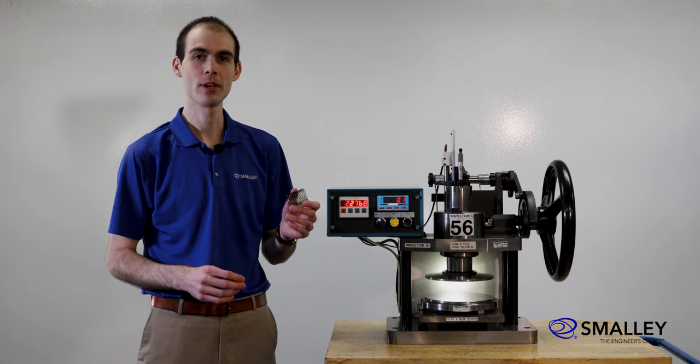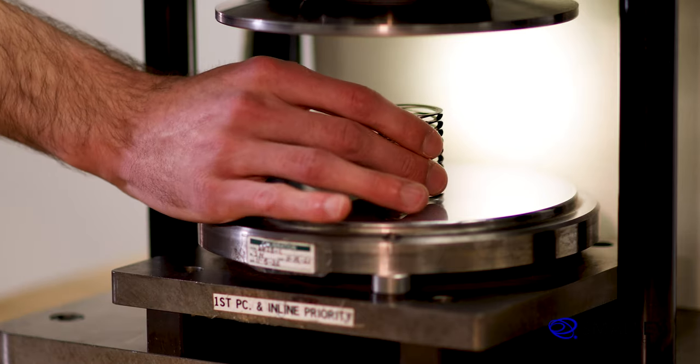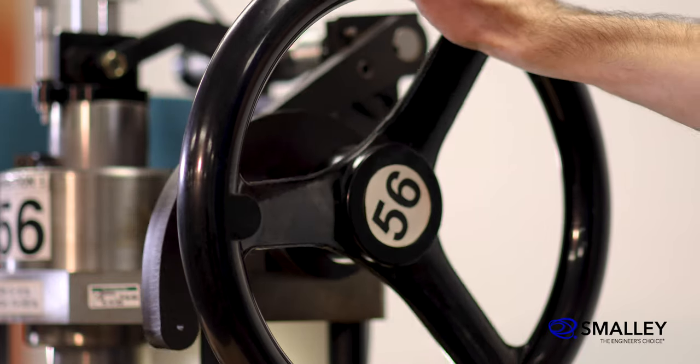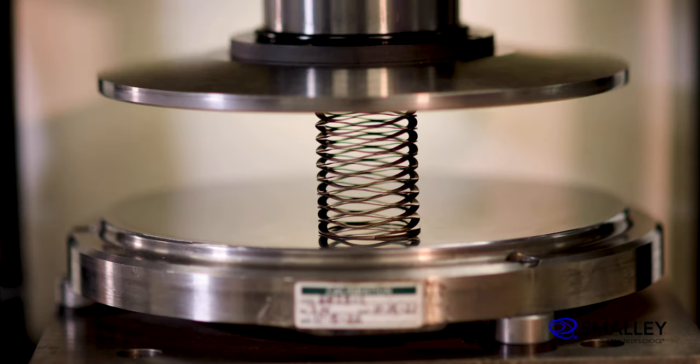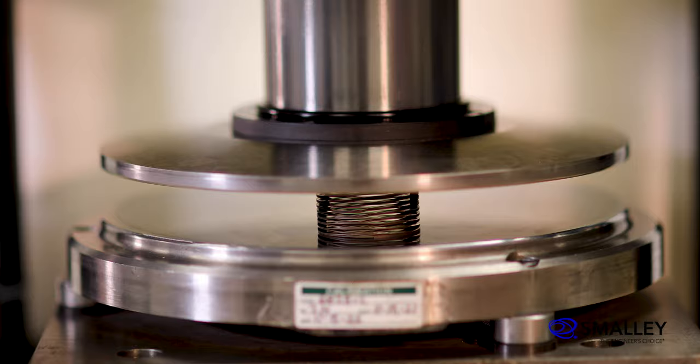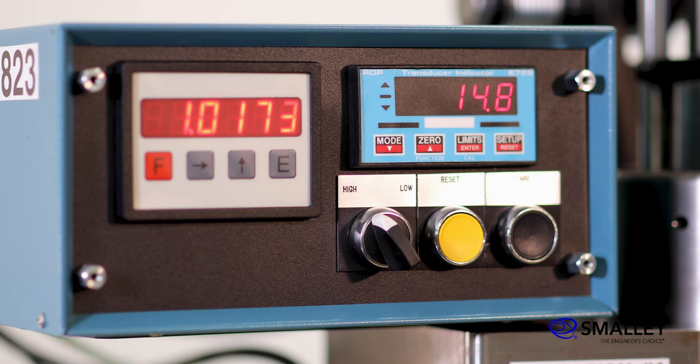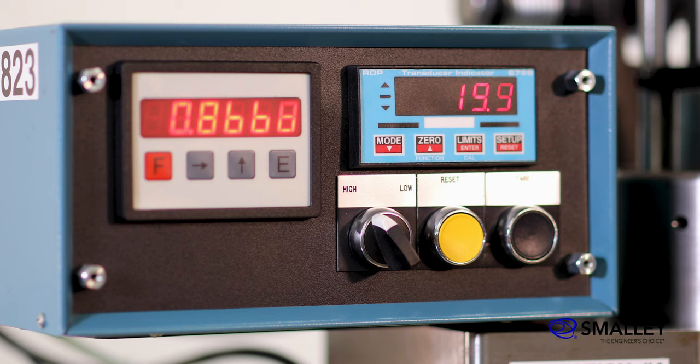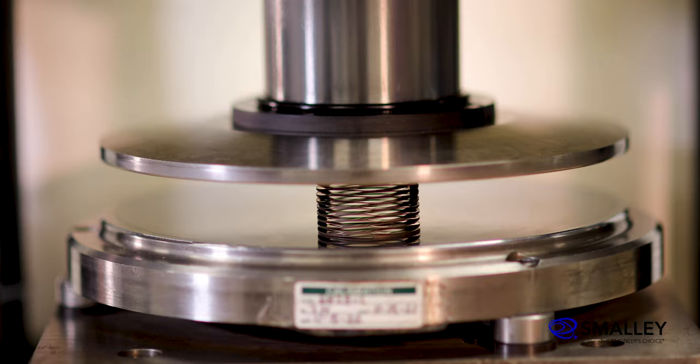To inspect the spring, I'll place it between the parallel plates and lower the upper plate using this wheel. As the upper plate contacts the spring, you can see the load readout increasing. At a height of 0.866 inches, the load came in at 19.9 pounds, which is in tolerance.